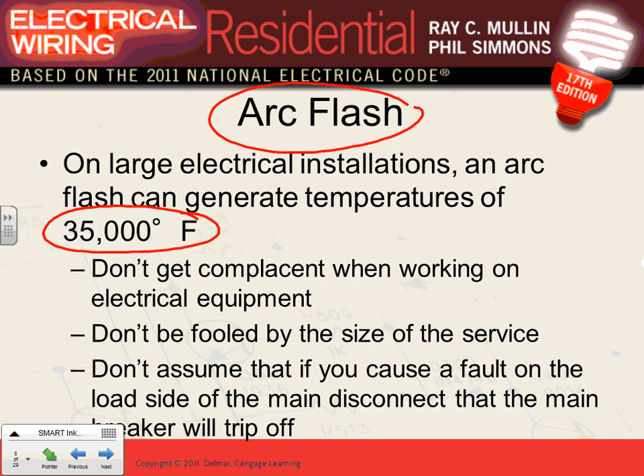Any question, guys, about arc flash? Just be aware. If you have no business there, especially when they open a panel, move away. You can stand in front of a panel like this with no problem, but the minute they open the box and you're exposed to energized equipment, if you have no business, move away. A good journeyman will move everybody away, the public has to be removed, and you have to barricade yourself when working on energized equipment. There are rules, take it very, very seriously as designers.